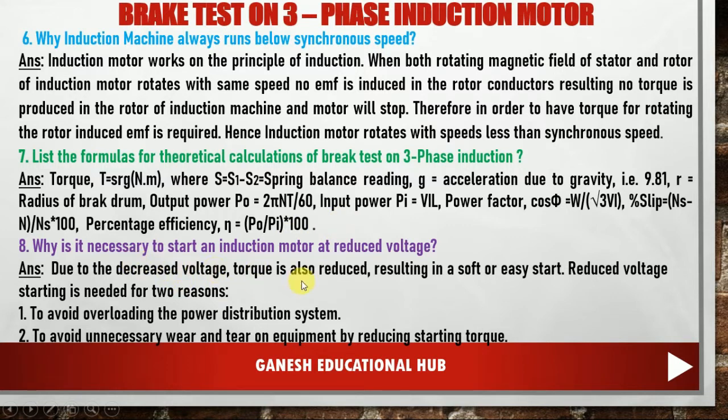Why is it necessary to start an induction motor at reduced voltage? This is also most important. Due to the reduced voltage, the starting torque is also reduced, resulting in a soft or easy start. Reduced voltage starting is needed for two reasons. The first is to avoid overloading the power distribution system, and the second is to avoid unnecessary wear and tear on equipment by reducing starting torque. Thank you.